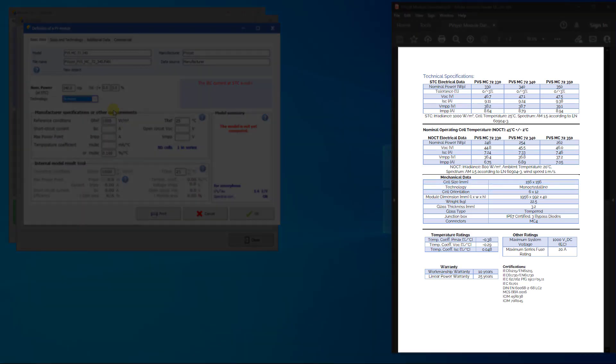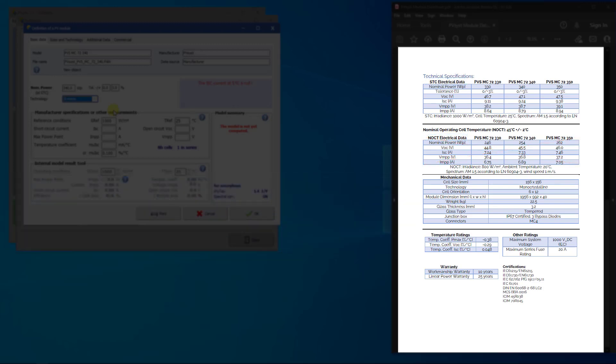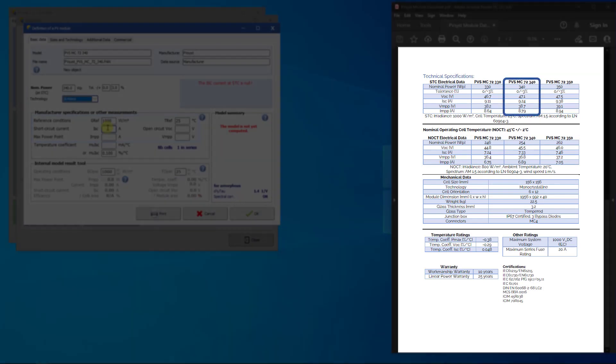Manufacturers will often supply both measurements at STC and NOCT. PVSyst only uses STC measurements to build a model of the PV module. You can disregard the NOCT measurement when creating a PAN file. So now, we will add the measurement at STC in PVSyst.